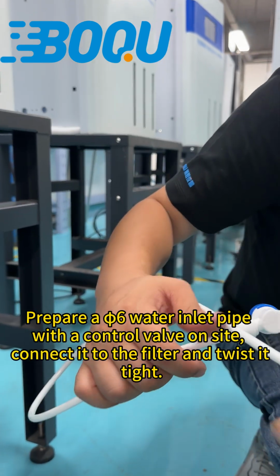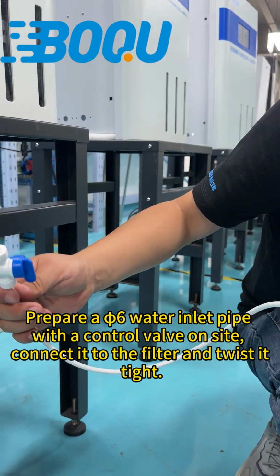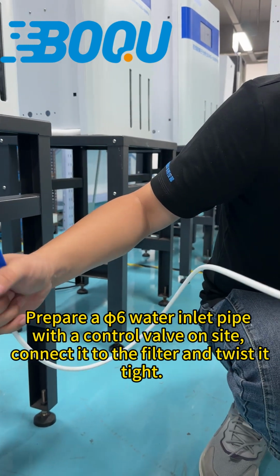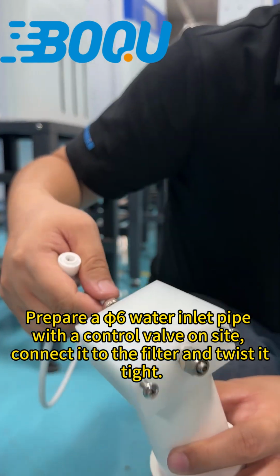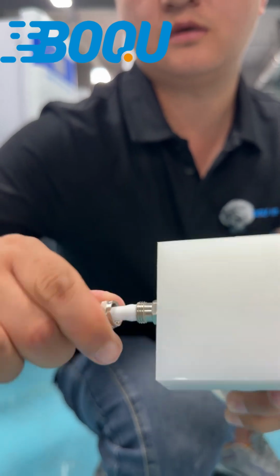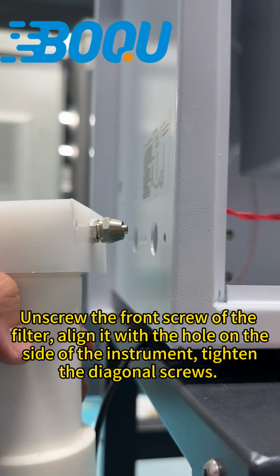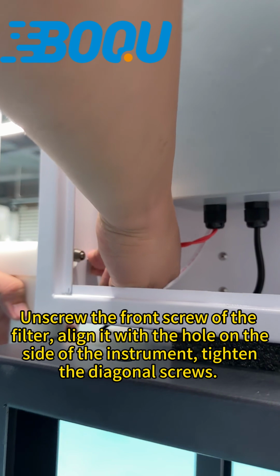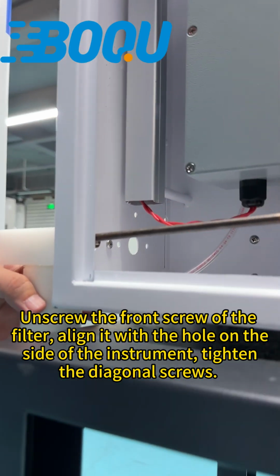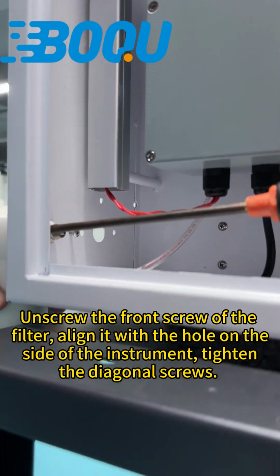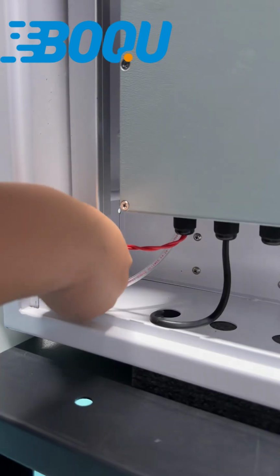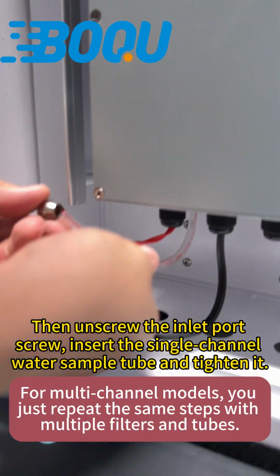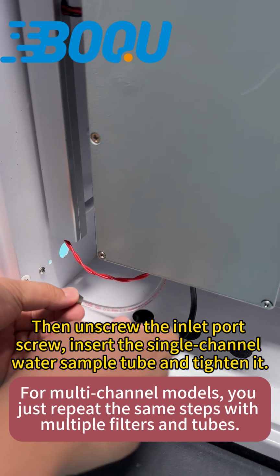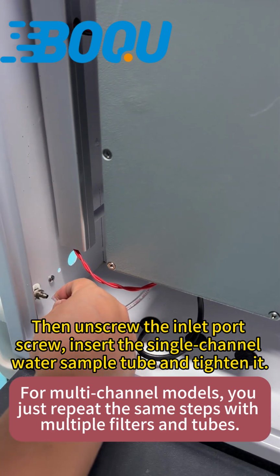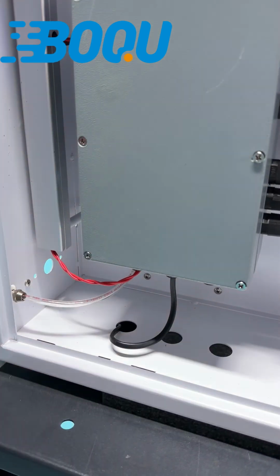Prepare a φ6 water inlet pipe with the control valve on site. Connect it to the filter and twist it tight. Unscrew the front screw of the filter. Align it with the hole on the side of the instrument. Tighten the diagonal screws. Then unscrew the inlet port screw. Insert the single-channel water sample tube and tighten it.